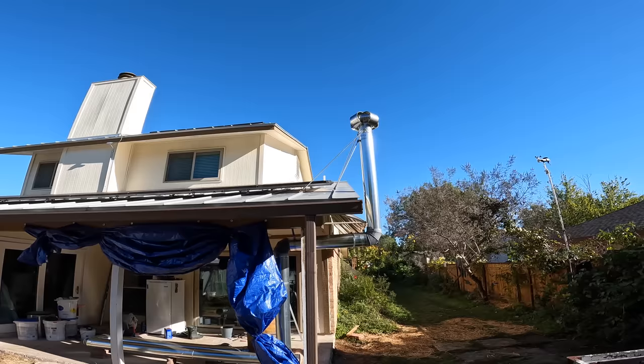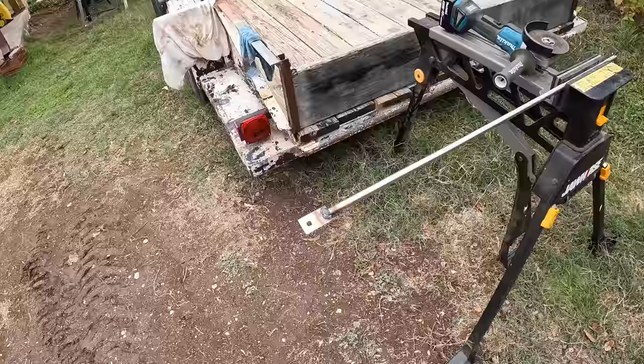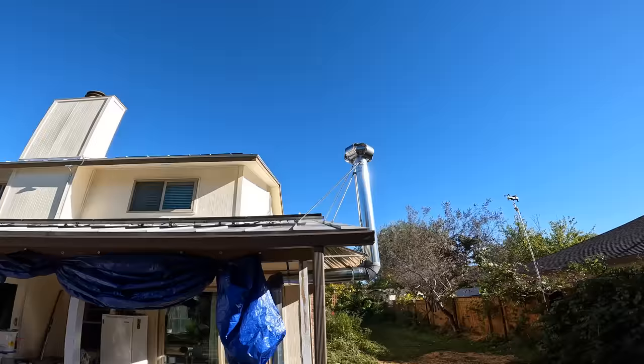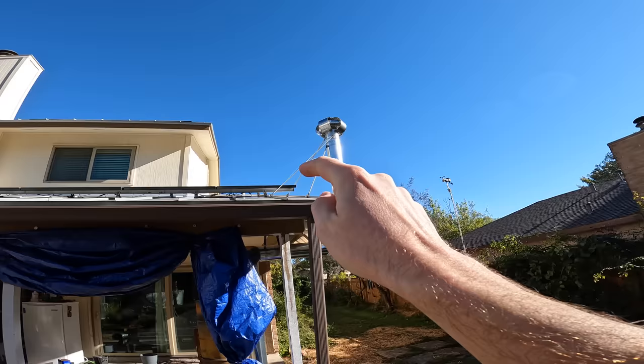I also picked up some stainless steel rods, you can see here. I got a piece of sheet steel that's also stainless, and I cut tabs out of the stainless steel sheet, and I welded those tabs to the rod on both ends. So one end bolts to the clamp, and one end bolts to some bolts that were passing through the ductwork up top. I decided to use a total of 3 different rods. These two here help control the pitch so the chimney doesn't fall outward. And then there's one going up onto the roof that controls the pitch going back and forth.